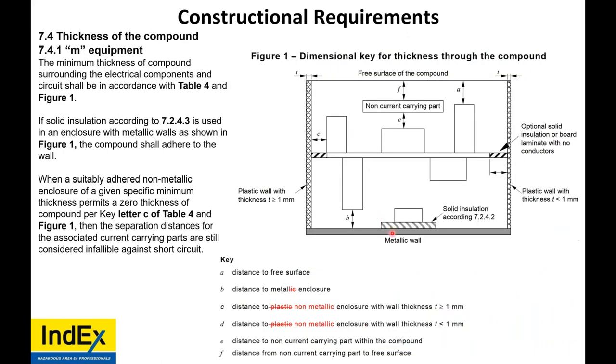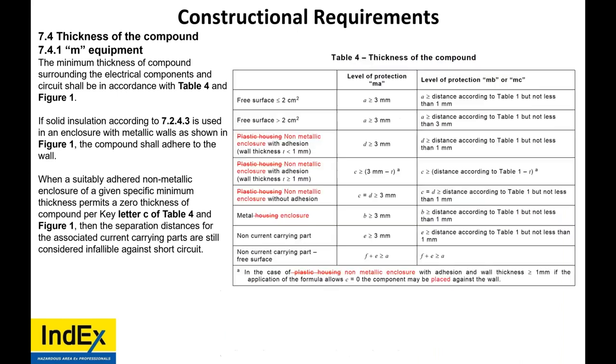Now, a visual indication of thickness requirement, wall thicknesses. It's in the standard, figure 1. The minimum thicknesses of compounds, of walls, and everything is listed. Now, what about the actual thickness of the compound itself? Well, you saw the figure. Now it starts going into other calculations and requirements. Basically, minimum 3 millimeters is a good measurement to have, and perhaps it could be more.